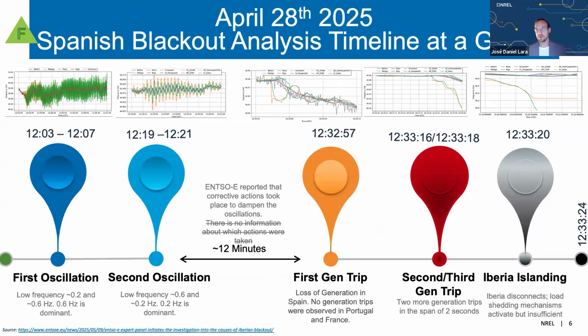By the time we put together this slide the first time, we had a hypothesis about certain things that happened in between the oscillations, in those 12 minutes before the first generation trip and the second oscillation ending. One hypothesis was that there were likely several operations taken by the operator in the grid to try to dampen those oscillations, and that those operations could have had effects that drove the first generation trip. Now that we have the full report, we can discuss what those operations actually were.